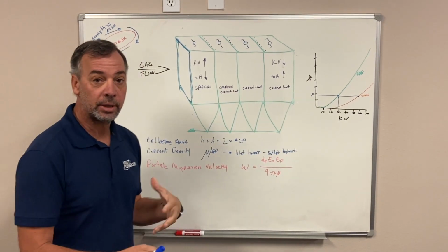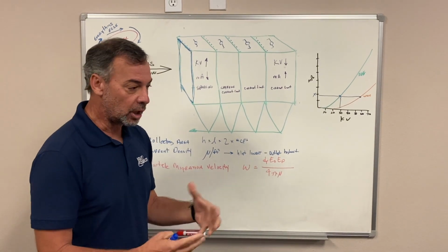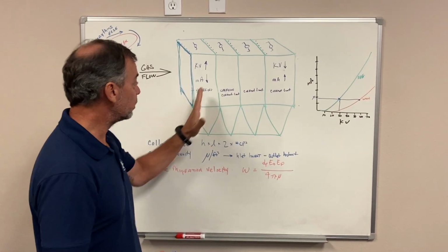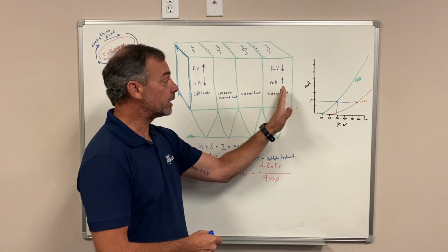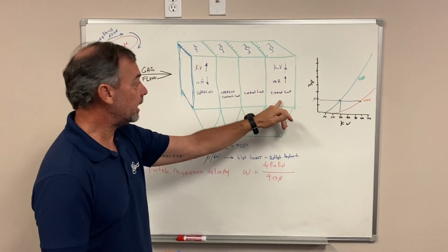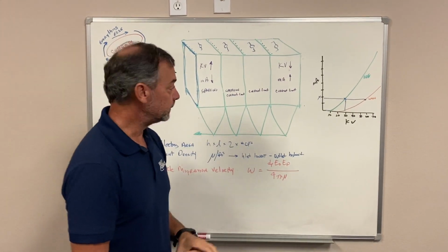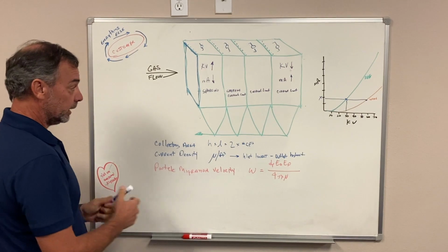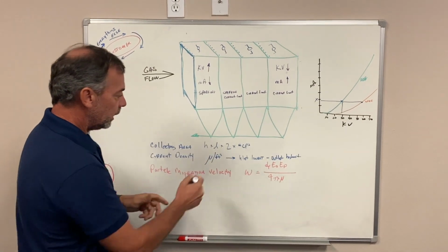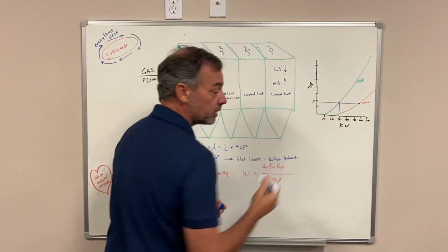And that's because of particulate loading. It also has a lot to do with the diameter of the particle. Your larger diameter particles are going to get collected early on, and it's your fine particulate at the end that is really causing the high opacity, but it's your fine particulate at the end that takes the most amount of current availability.